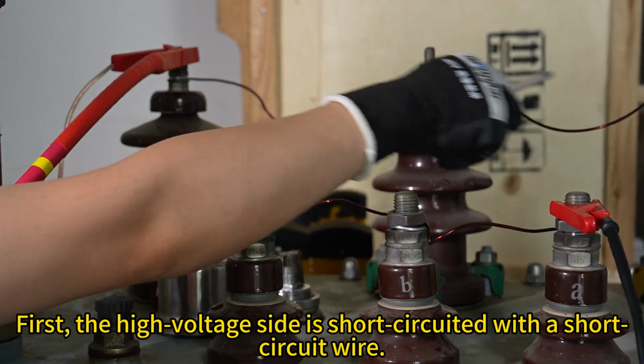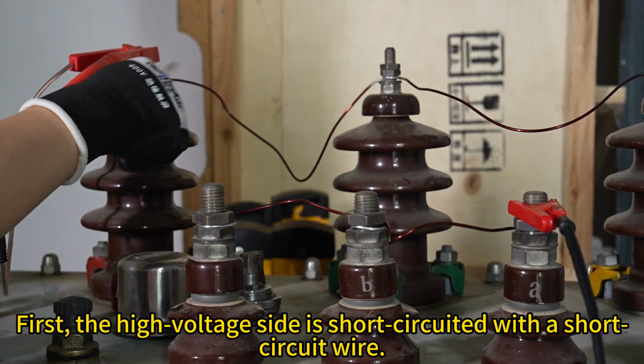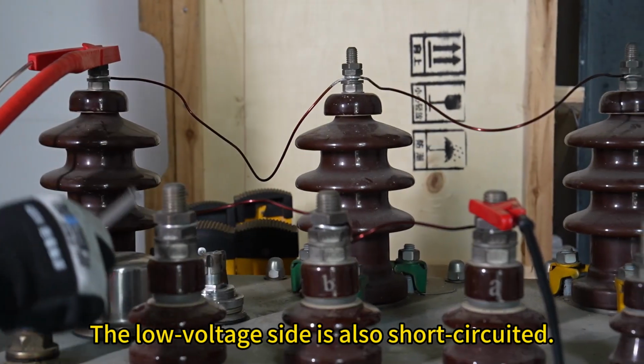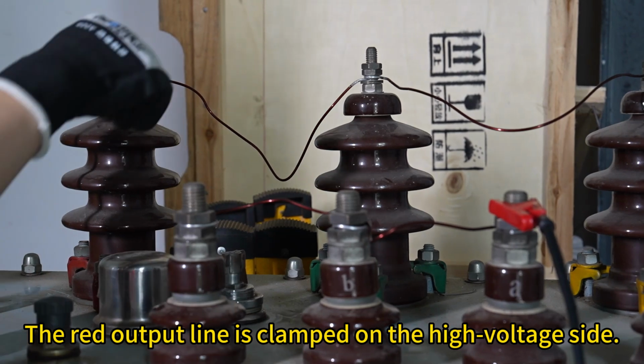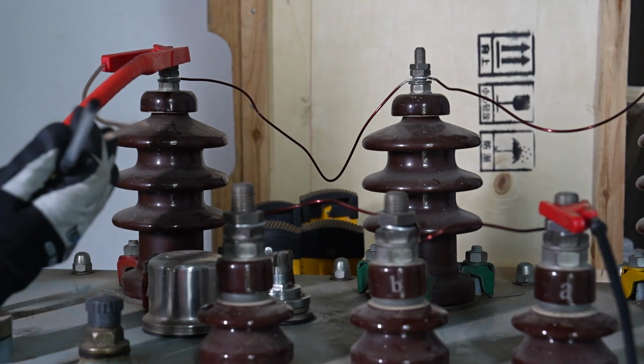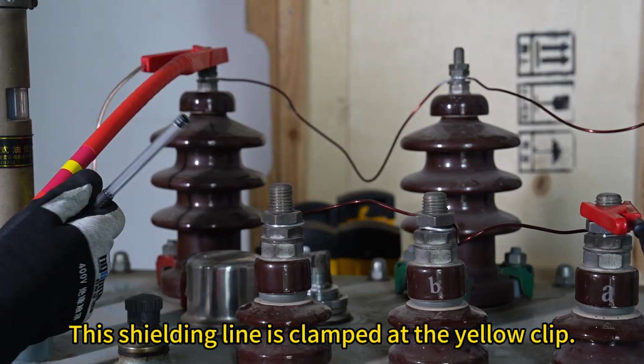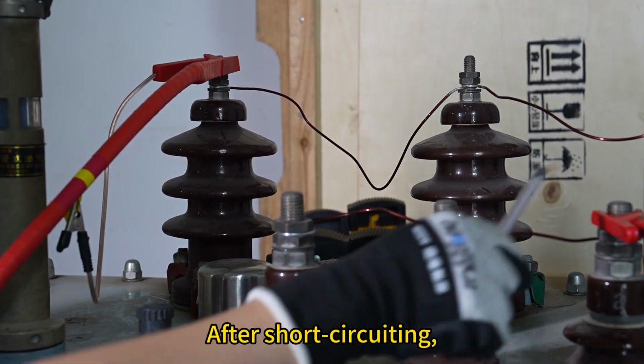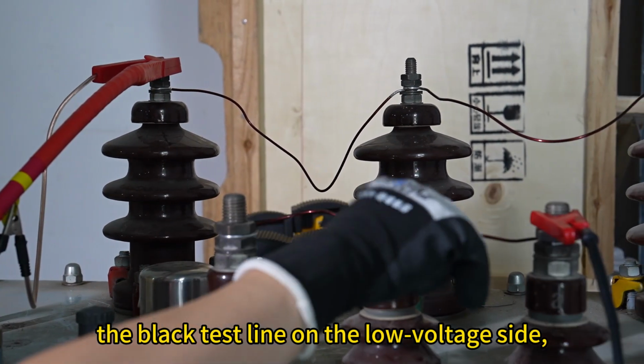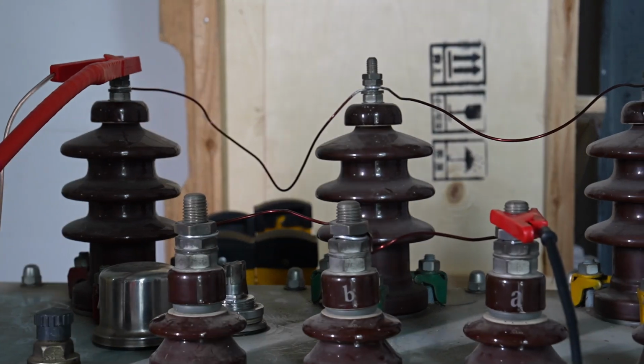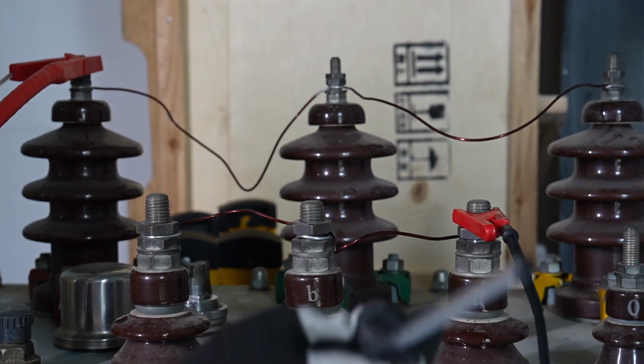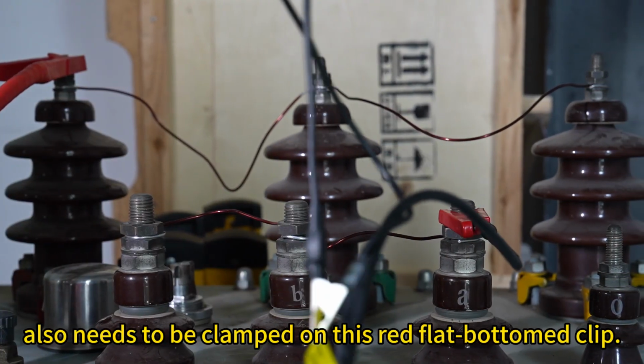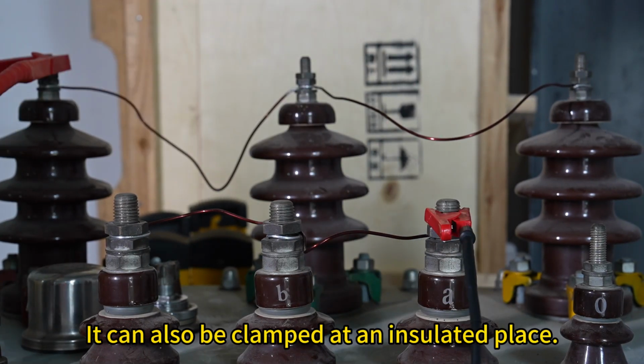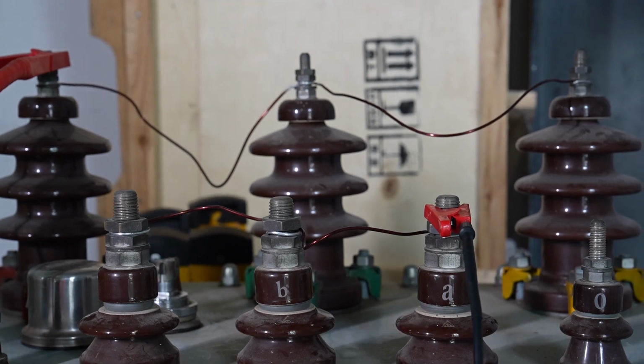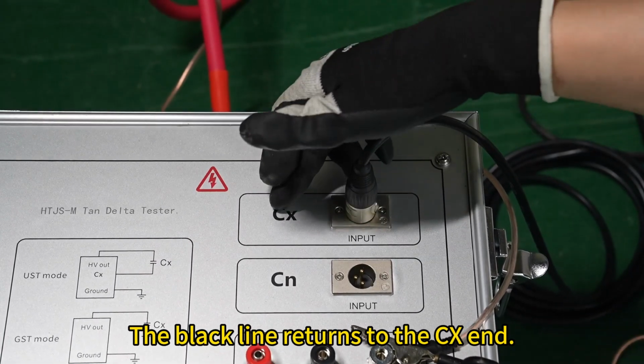First, the high voltage side is short-circuited with a short-circuit wire. The low voltage side is also short-circuited. The red output line is clamped on the high voltage side. This shielding line is clamped at the yellow clip. After short-circuiting, the black test line on the low voltage side then returns to the instrument. Note that this small black clip also needs to be clamped on this red flat-bottomed clip, or it can be left hanging. It can also be clamped at an insulated place. The black line returns to the CX end.